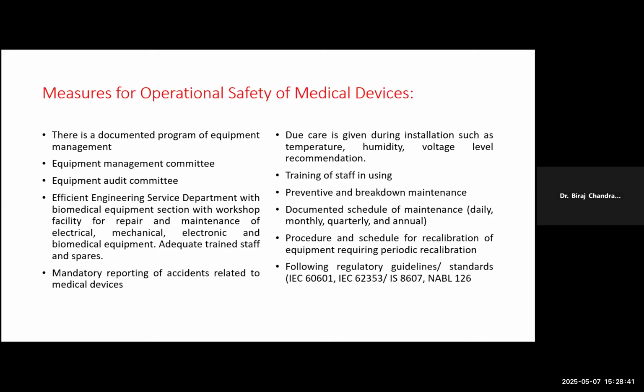It is almost always seen that these are the neglected parts. So we don't care about the maintenance of the equipment. No, that should not be the case. There should be a well-defined workshop. At the state level, it may cover all the districts and compile all the medical devices for calibration, EMC and so on, or at the district level they may have centralized arrangements. But there should be workshops for electrical, electronic, and biomedical work. Then a mandatory reporting system, that is the materiovigilance program. Then due care must be taken during installation, such as temperature and humidity requirements, and there should not be any voltage fluctuation.